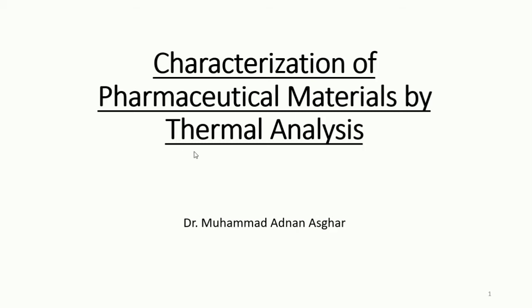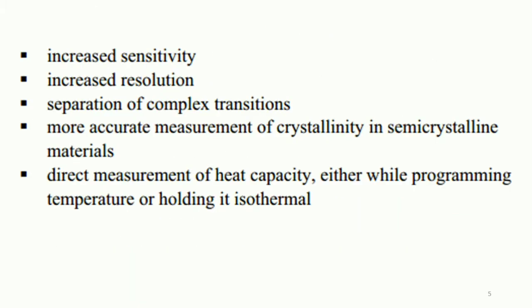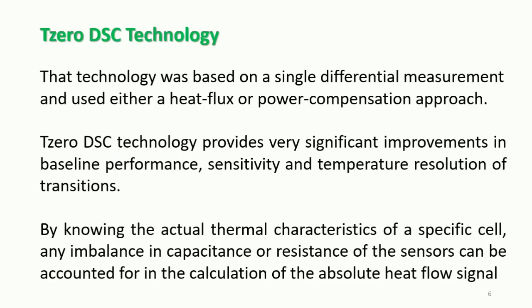So far we have discussed pharmaceutical materials and some research advances in differential scanning calorimetry (DSC) techniques. We have already discussed modulated DSC, which gives increased sensitivity and increased resolution while allowing separation of complex transitions, along with accurate measurements of crystallinity in semi-crystalline materials. The T0 DSC also helps improve baseline performance, sensitivity, and temperature resolution of transitions.